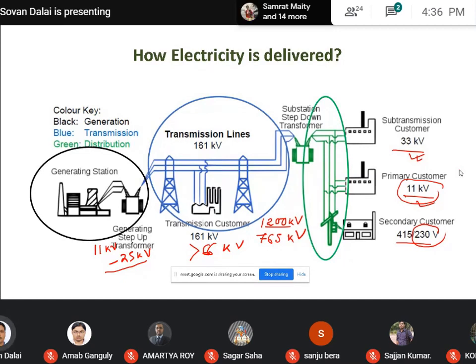But why is the generating voltage level like this, and why is the transmission voltage level like that? There is a certain reason behind this. Generating voltage is limited, very low compared to the transmission voltage level, because it depends upon the alternator rating. If you go for a higher voltage level, the overall size of the alternator increases, and it is not economical to design an alternator above that voltage.